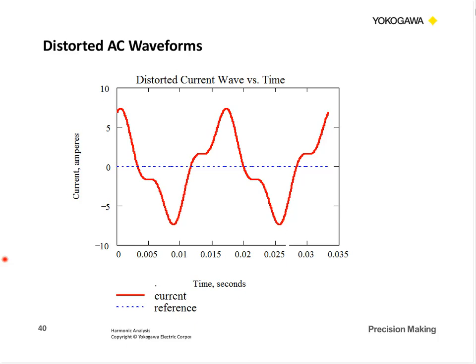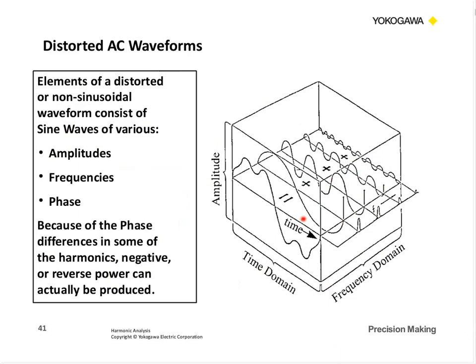So here's what we'll talk about, a non-sinusoidal waveform. And this could represent a current waveform versus time. So we don't have our nice clean sine wave, we've got something that's all distorted. So if we break this down and analyze it, the distorted waveform is made up of various waveforms, various amplitudes, various frequencies if we look at this in the frequency domain, and different phases. And probably can't see too much of a phase shift here, but those three parameters are what, if we break down that waveform and look at individual waveforms, all these would add up together to give you this resultant distorted waveform. So in the time domain, this is our result, and then we can break it down in the frequency domain into various sine waves of various amplitudes, frequencies, and phase.